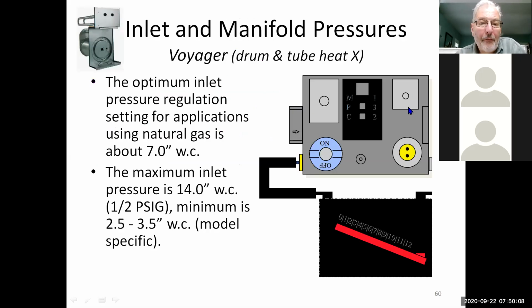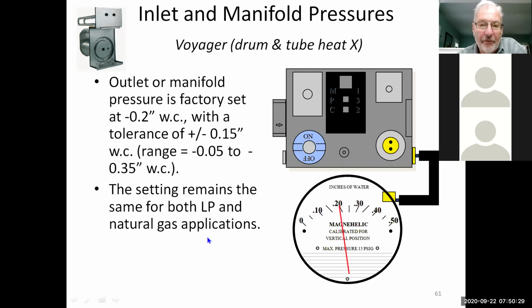When we're dealing with manifold pressure, on natural gas, or for that matter, natural and LP, 7 inches is our optimal pressure for inlet pressure, and 0.2 negative is going to be our negative pressure. Now, when you start these units, what you're going to see is the gauge inducer come on.